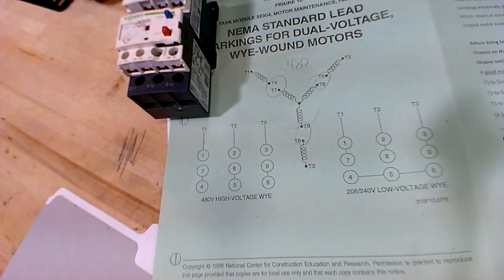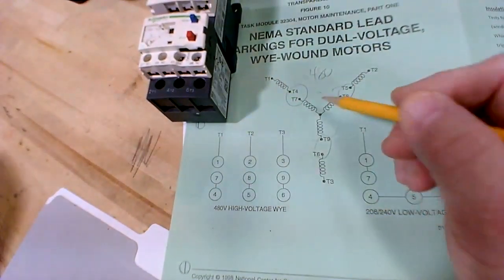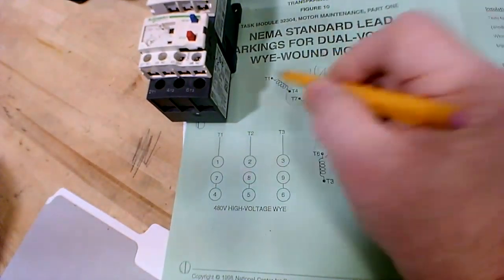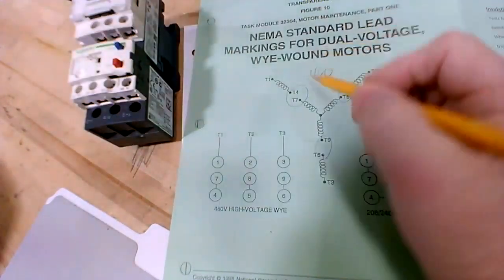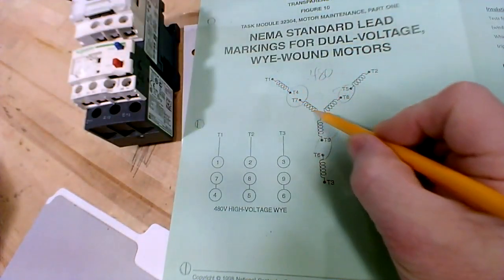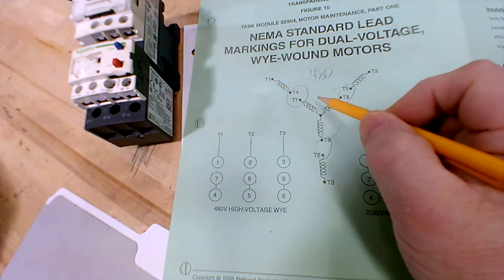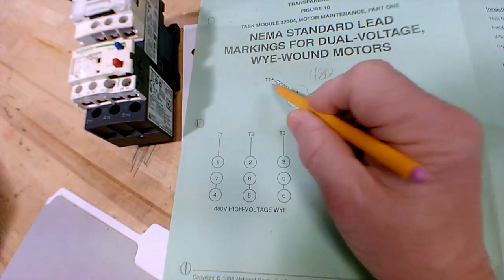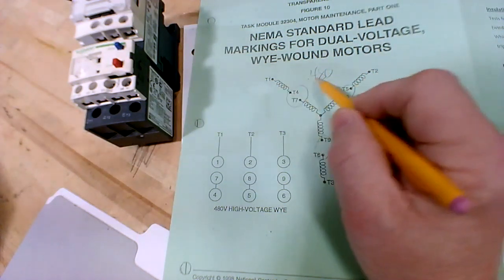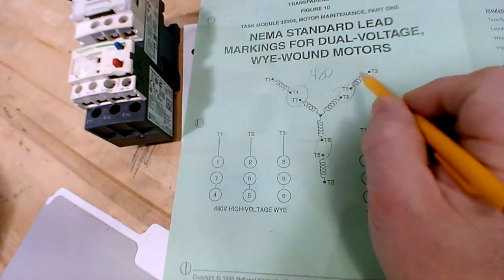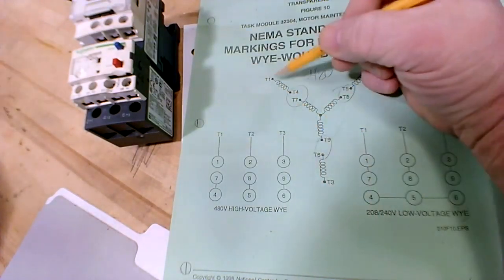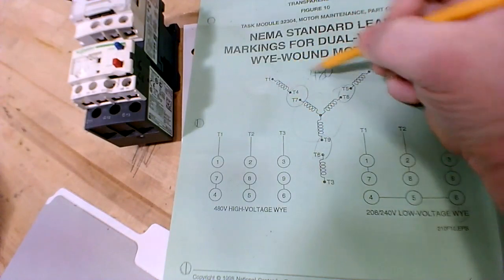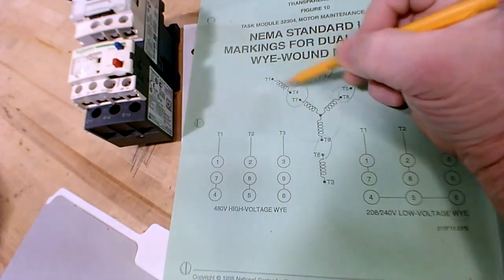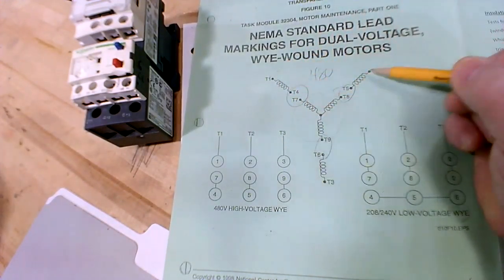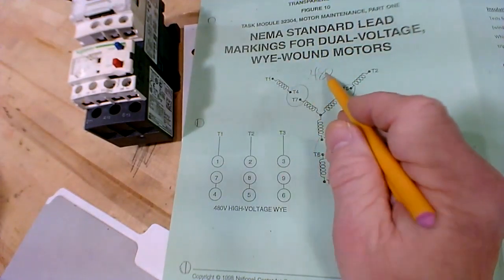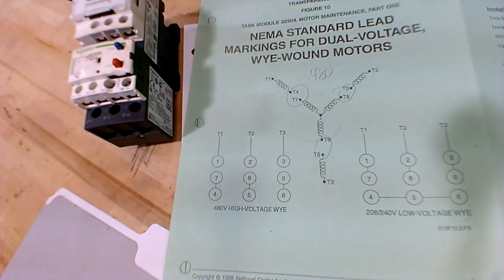Let's do a breakdown of this. Now, if you have 480 volt across here, and you have 4 windings in series in that set there, and I measure 480 across there. And we know in a series circuit, if you've got 4 coils in there and they're the same resistance, the voltage is going to divide up in 4. You'll drop a quarter of it here, a quarter there, a quarter there, and a quarter there, right? So what's a quarter of 480? 480 divided by 4.